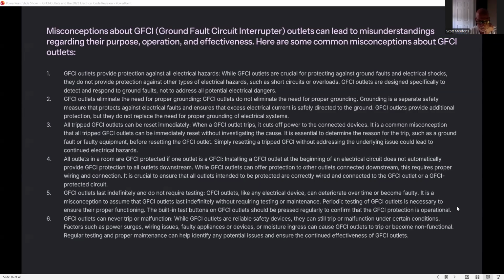GFCI outlets eliminate the need for proper grounding. As we talked about, you've got to have proper grounding. Grounding is a separate safety measure that protects against electrical faults and ensures that excess electrical current is safely directed to the ground. GFCI outlets provide additional protection, but they do not replace the need for proper grounding. As we talked about in the bathroom, that is non-grounded, but it's GFCI protected.